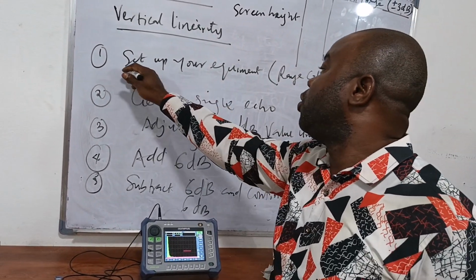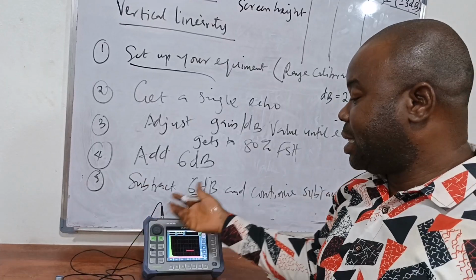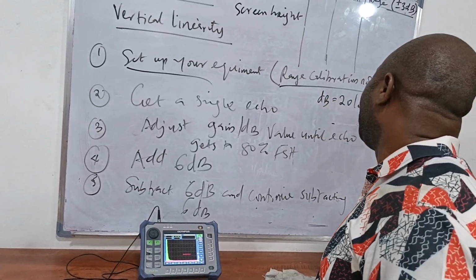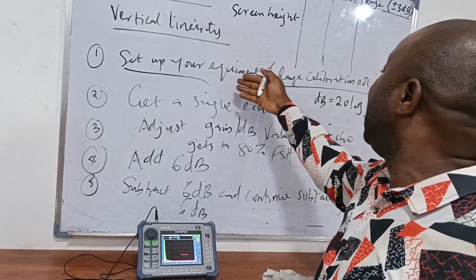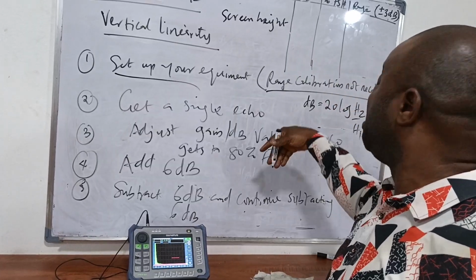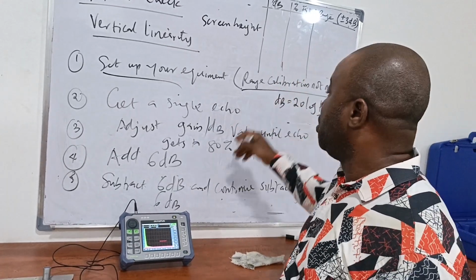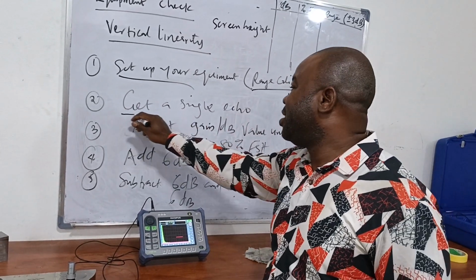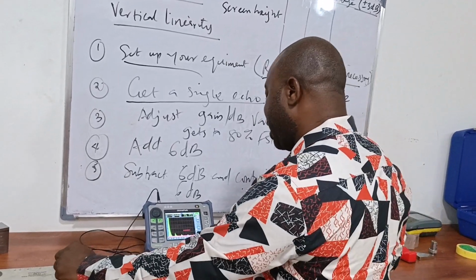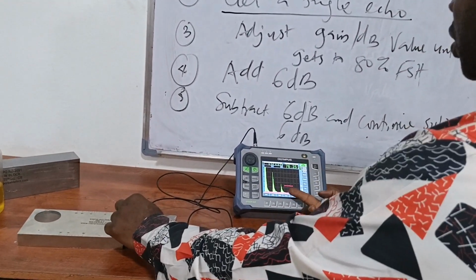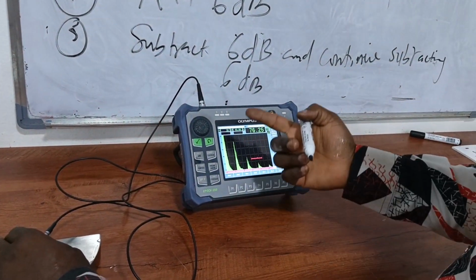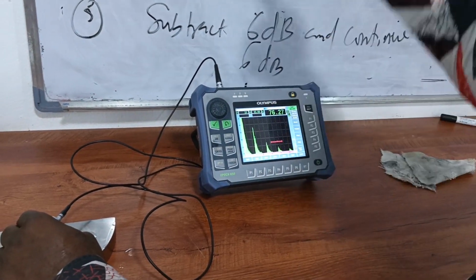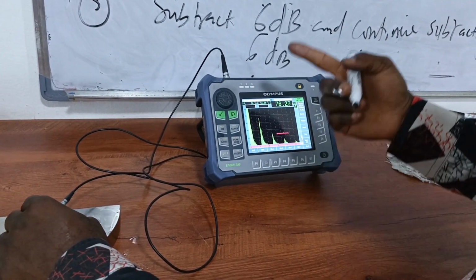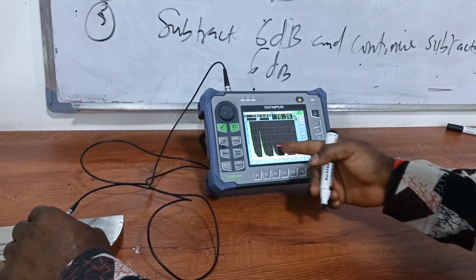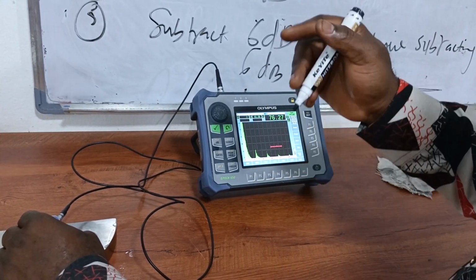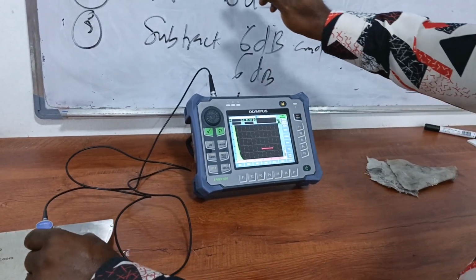So how do we go about it? You need to set your equipment up. Just basic setup. Range calibration is not necessary. To do your vertical linearity, you don't have to do your range calibration. But if you still do your range calibration, all good. Then get a single echo. In this case, we have about 4 echoes here. We can use any of them to do our vertical linearity check. So you don't need to use all of them. Just one is enough.